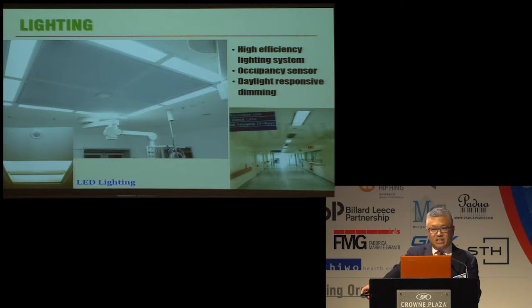As I mentioned before, lighting accounts for 18% of electricity use in hospitals. T5 fluorescent lamps with electronic ballasts and also compact fluorescent lamps have already replaced the old T8 fluorescent lamps and incandescent lamps. But with the improved quality and lower cost of LED lamps, they are becoming the preferred lighting solution to reduce the lighting power density because of their superior performance and longer service life. Lighting control using occupancy sensors for rooms that are not in use, although they are not preferred by Dr. Long earlier on, as he mentioned, and also using dimmers for daylight harvesting control can help further reduce energy consumption of lighting installations. Less waste heat from the lighting installation means lower cooling load to be handled by the HVAC systems.